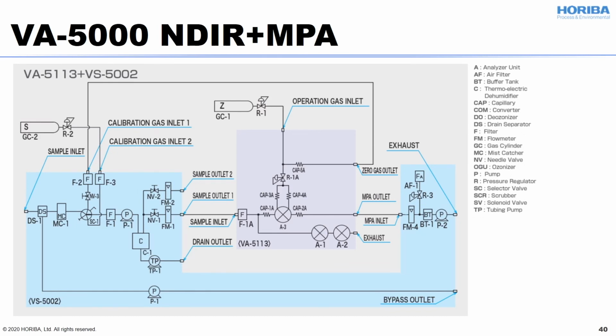Alright, let's go from the sample inlet, going through a drain separator to knock out the moisture, and the mist catcher, and the line selector is right there, and filter and a pump, and the cooler unit is always saturated at 5 degrees C to drop the moisture. Like I said earlier, you can hook up with another VA-5000.